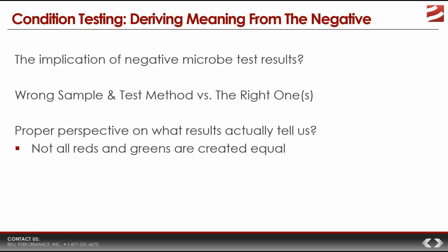The culture test was done on a fuel sample. You had to take a sample to do it, and then you did a culture test on that sample. But what if that sample was not a good representative sample? The conditions of the tank are different, so the sample's wrong, and that was a reason why your results were wrong.